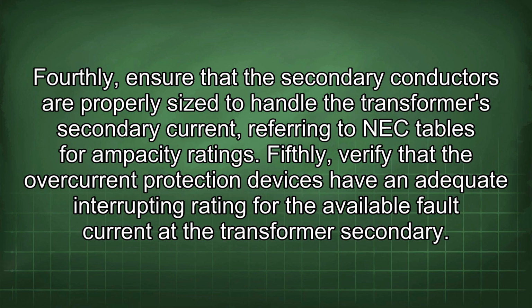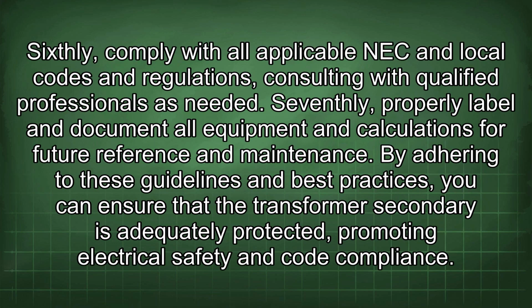Fourthly, ensure that the secondary conductors are properly sized to handle the transformer's secondary current, referring to NEC tables for ampacity ratings. Fifthly, verify that the overcurrent protection devices have an adequate interrupting rating for the available fault current at the transformer secondary. Sixthly, comply with all applicable NEC and local codes and regulations, consulting with qualified professionals as needed. Seventhly, properly label and document all equipment and calculations for future reference and maintenance. By adhering to these guidelines and best practices, you can ensure that the transformer secondary is adequately protected, promoting electrical safety and code compliance.